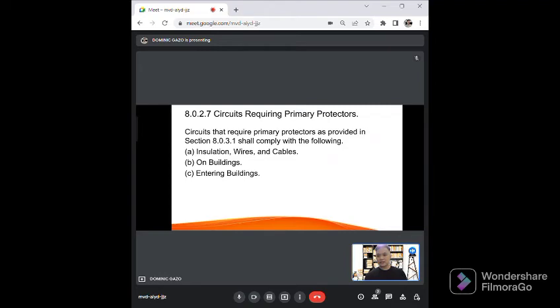And next for this article, 8.0.2.7, circuits requiring primary protectors. Circuits requiring primary protectors as provided in section 8.0.3.1 shall comply with the following. For A, insulation of wires and cables: these communication wires and cables without metallic shield, running from the last outdoor support to the primary protectors, shall be listed. And on the buildings, communications wires and cables shall be separated at least 100 millimeters from electric light or power conductors.